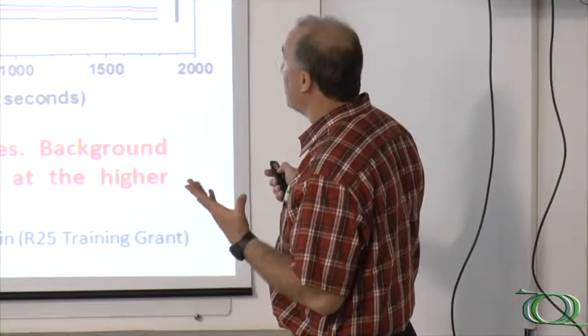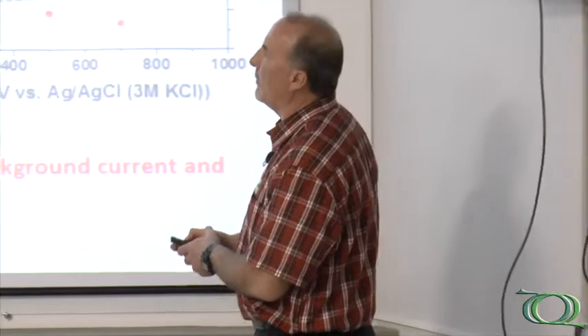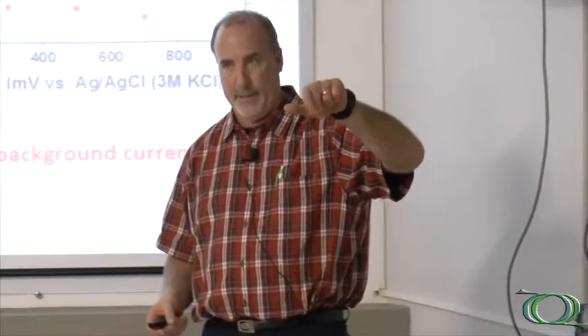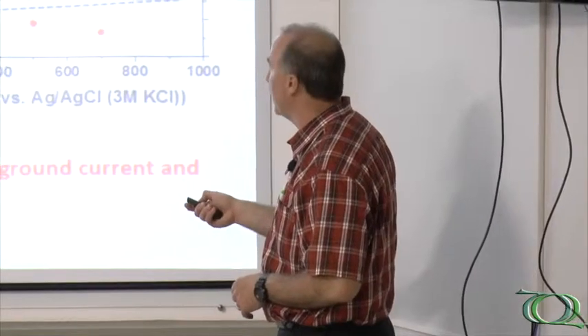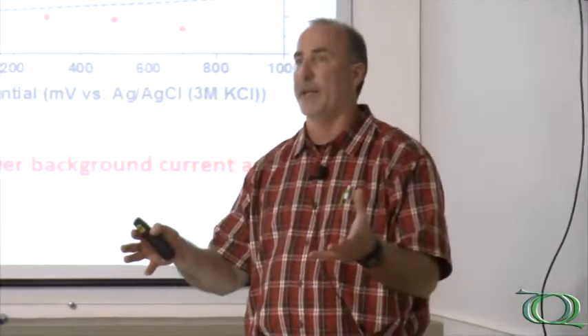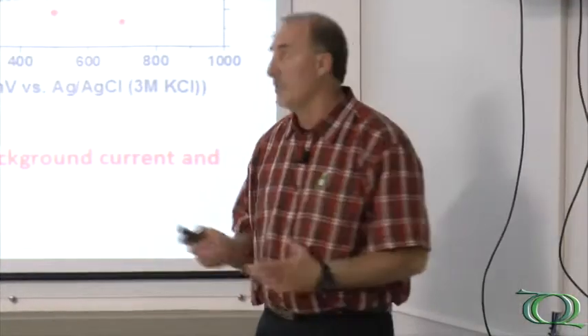The current increases with potential as expected. Looking at the background current at the end of the detection period as a function of potential: the red dots are for the TAC electrode, the black dots for diamond. At all potentials, particularly at high potentials, the TAC materials have background currents that are two to three times lower for the same area. The noise — the standard deviation about the background current — is basically constant at about one nanoamp for all potentials for the TAC electrode, about five times lower than diamond. So without doing anything special to the electrode, we automatically have a five-times improvement in the signal-to-noise ratio, meaning detection limits can go down by a factor of five.